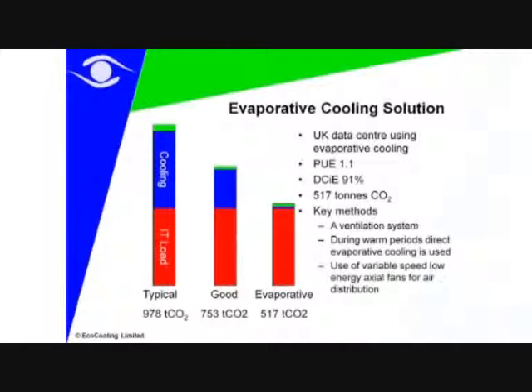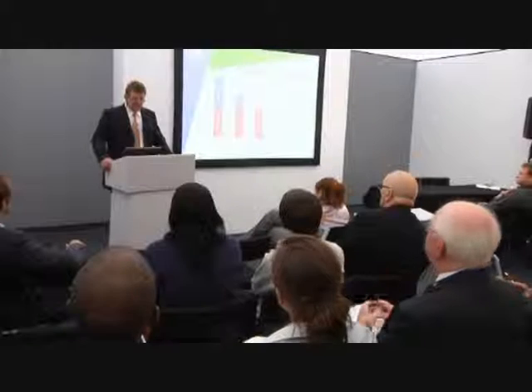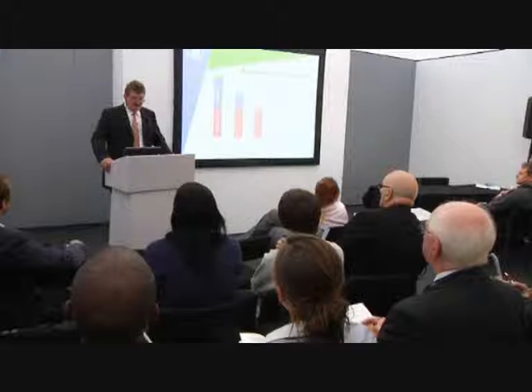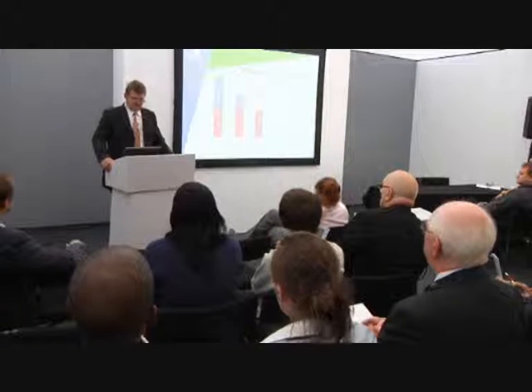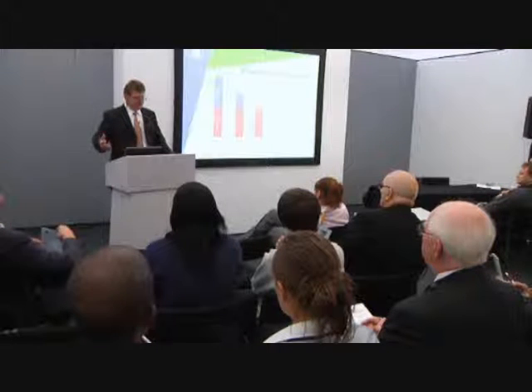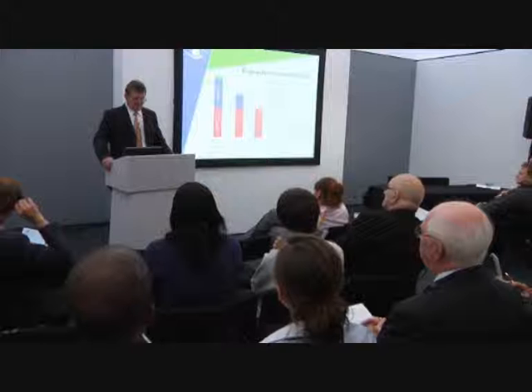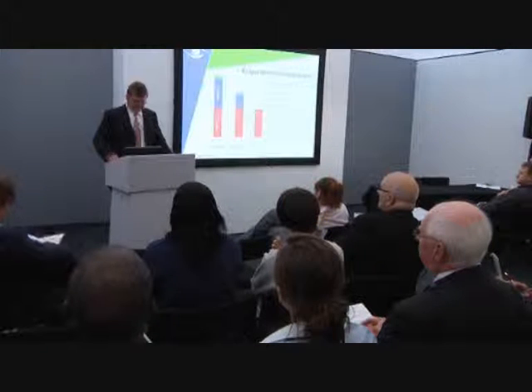So what can we do to improve things? If we use a ventilation system and use evaporative cooling instead of refrigeration, then it is technically possible to achieve a PUE of 1.1. That's an incredible level of saving, and in some cases, it looks too good to be true. But what I'll try and explain over the next few minutes is how we really achieve that using simple engineering and in a simple modular system designed specifically for the IT sector. At the end of the presentation there'll be an opportunity for questions, so please, if you could wait till then, it would make things a little bit easier for us in terms of presentation and timing.